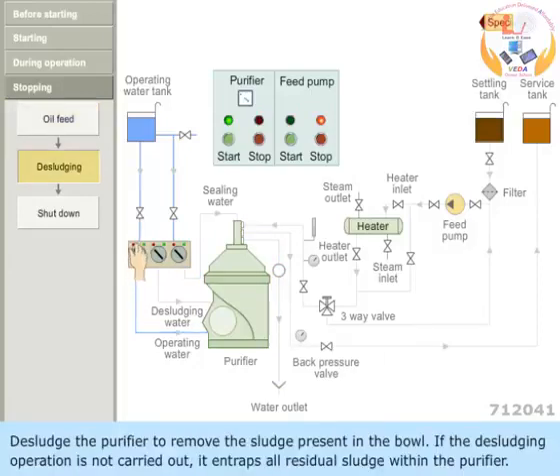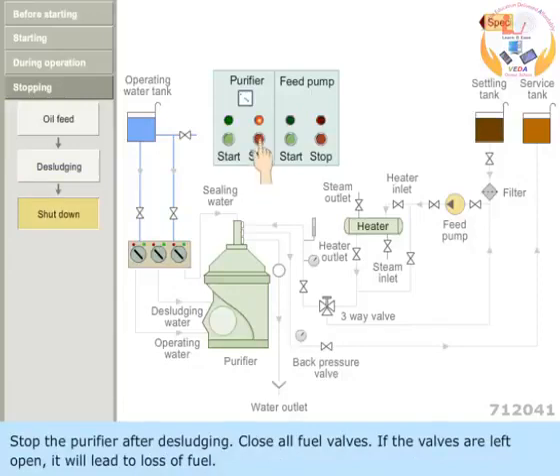Desludge the purifier to remove the sludge present in the bowl. If the desludging operation is not carried out, it entraps all residual sludge within the purifier. Stop the purifier after desludging.